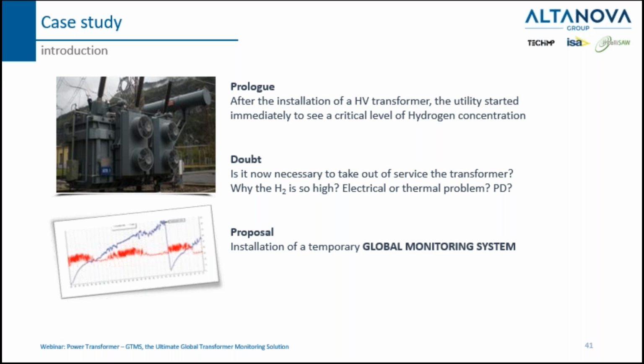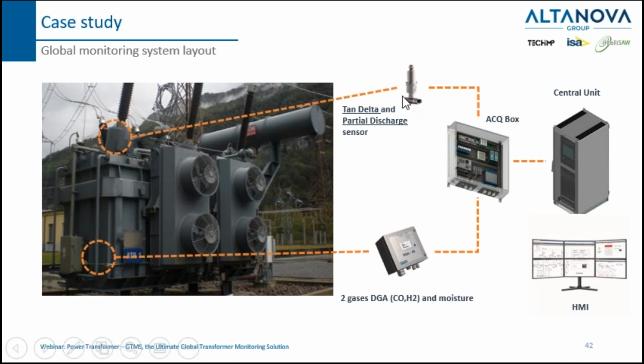In this case, we installed a global monitoring system temporarily, for a few months at the beginning. The global monitoring system was composed of three parts: tan delta and partial discharge sensors installed on top, on the bushing side; then a DGA with two gases, CO and hydrogen, plus humidity and temperature; then an acquisition unit connected to the central unit, and also a dedicated human machine interface.